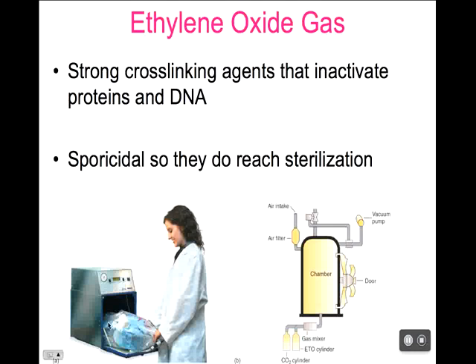So it looks sort of like a mini autoclave. You put your waste in there, right? And then it will mix the ethylene oxide gas and flood the chamber with the ethylene oxide gas, and that will sterilize. It will kill off anything that's inside of there. And then it's safe to throw that trash in the regular trash can. So some offices use ethylene oxide gas instead of an autoclave in order to sterilize. Ethylene oxide gas is also used in food prep and drug prep when you can't use heat or steam heat like an autoclave. You could use ethylene oxide gas to achieve sterilization.